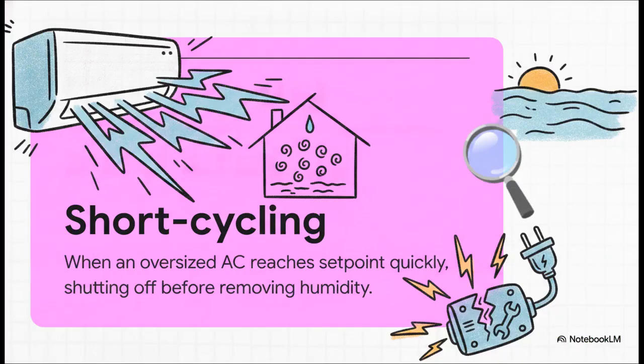The most crucial thing to remember is that bigger is definitely not better when it comes to AC. If your unit is oversized, you'll experience something called short cycling. This is when your AC blasts the house with freezing air, hits the target temperature on the thermostat in like 8 to 10 minutes, and then immediately shuts down. Because that cycle is so fast, the system never gets the chance to pull humidity out of the air. So your house feels cool, sure, but also terribly clammy. You'll really feel this in the mornings near the coast. Plus, all those constant start and stop cycles pull massive electrical draws and chew through your compressor's lifespan.